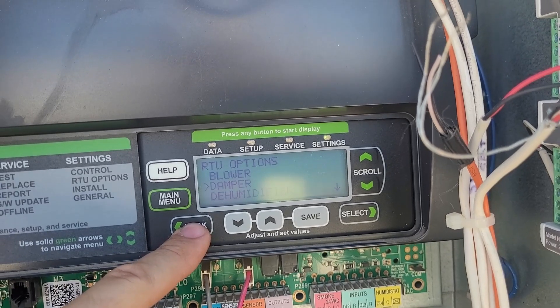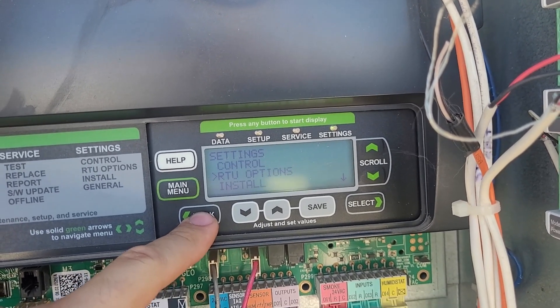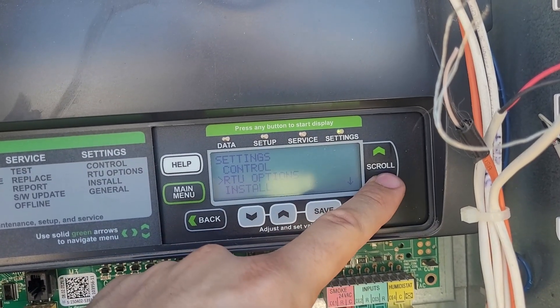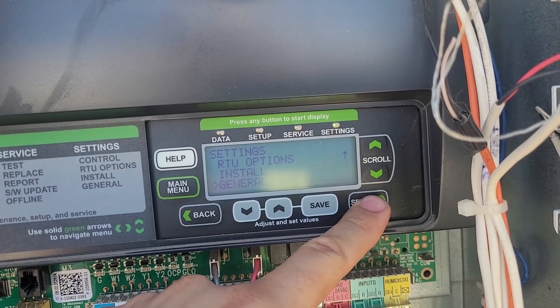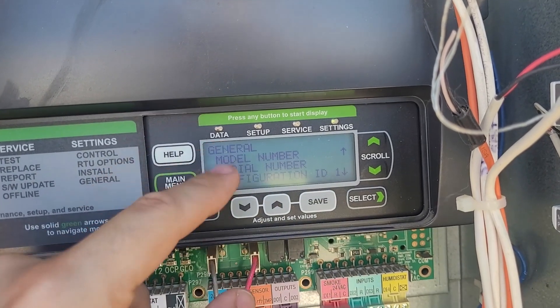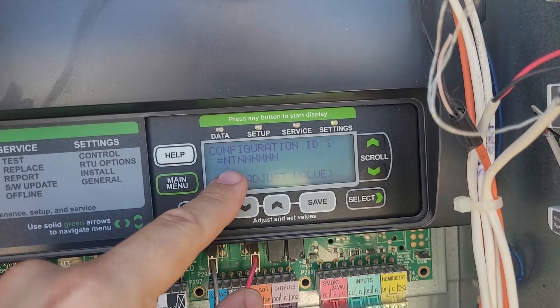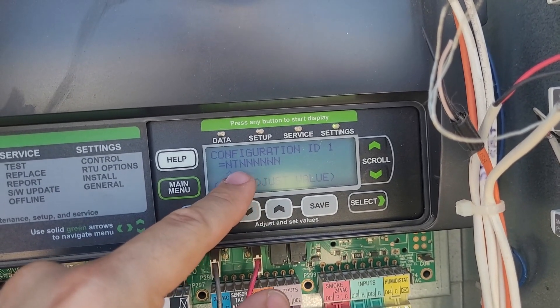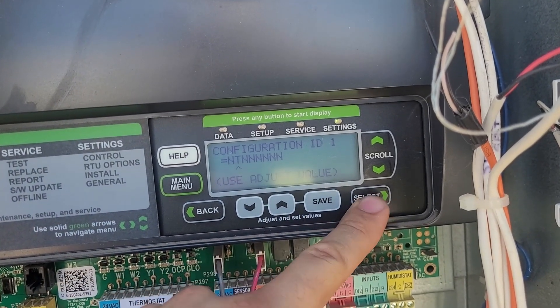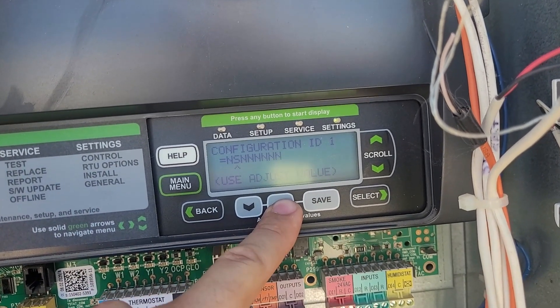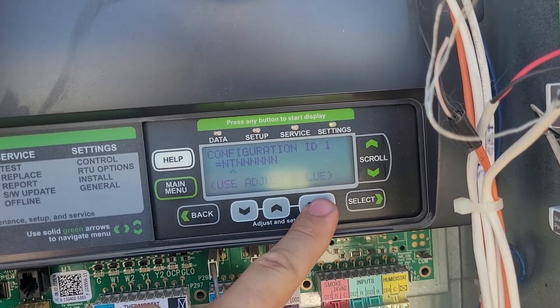Now I'll show you how to change from enthalpy control to temperature control. Go down to General — underneath Settings, go to General and select it. You can scroll down to Configuration ID number one, and the second digit or second place should be T. If it's something else like G for global or S for enthalpy, you're going to want to change that to T and press Save.